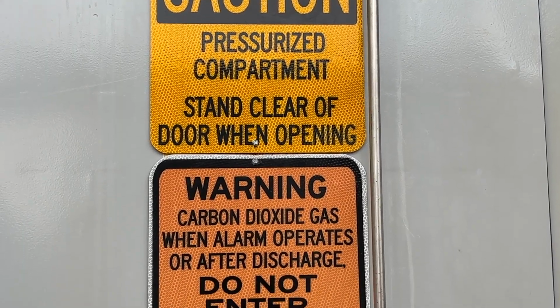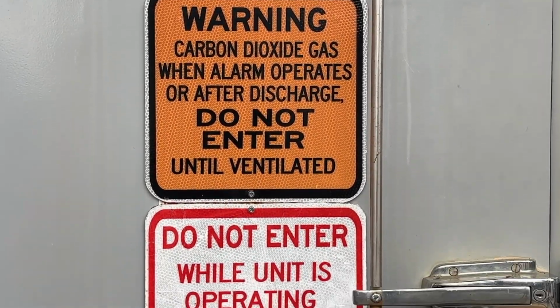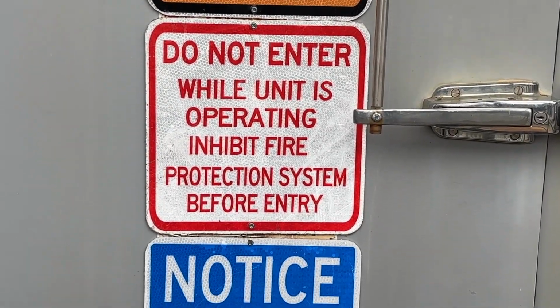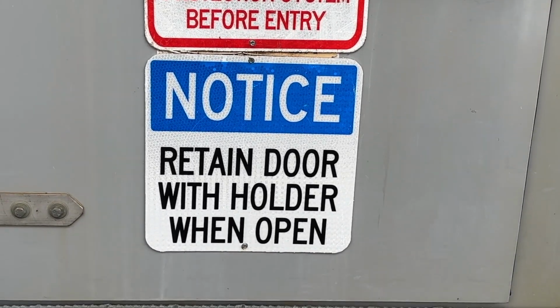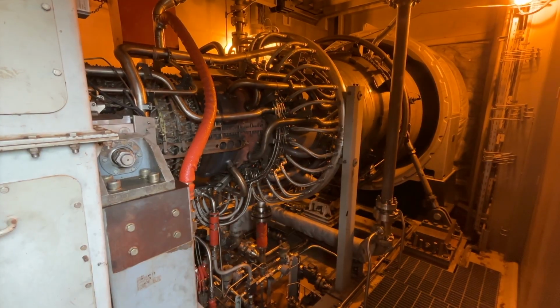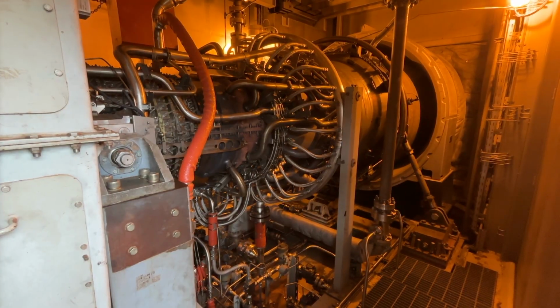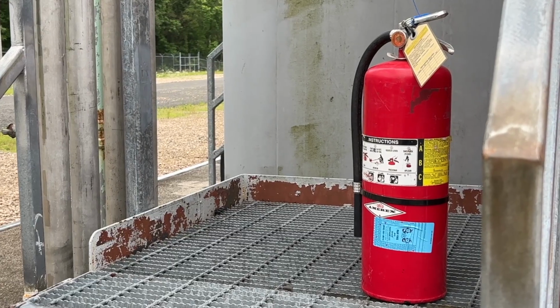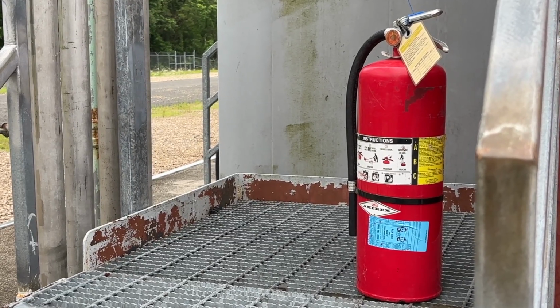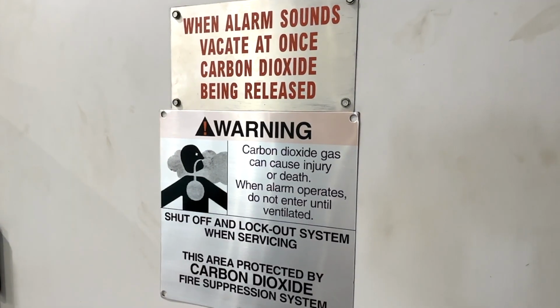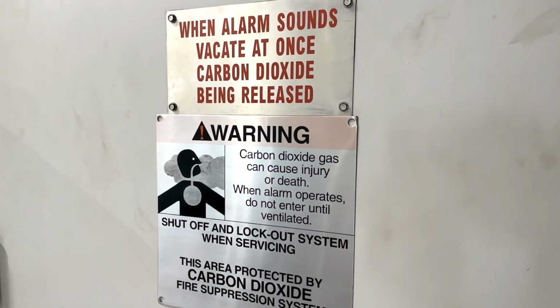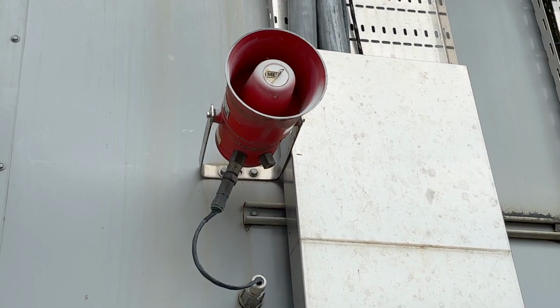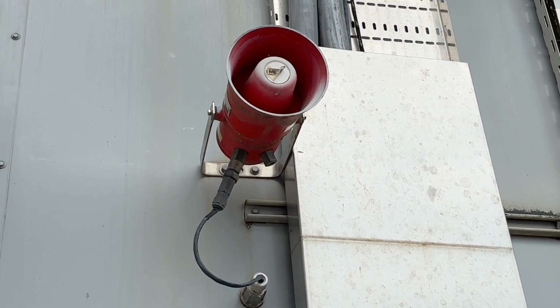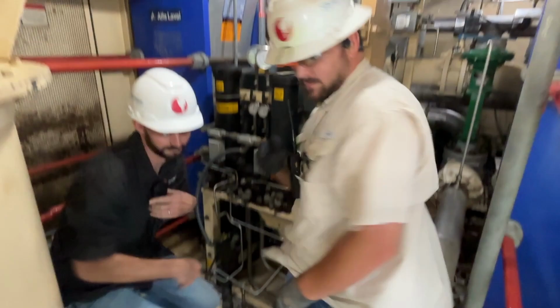In general, if you are working in an area that is protected by an automatically controlled CO2 system, the system will be disabled and valved out of service while you are working, in which case, depending on the nature of your work, you may be required to keep a hand-operated fire extinguisher on hand. In the event of a fire and the automatically operated CO2 system is not taken out of service, an alarm will sound a few seconds before the system discharges. Vacate the area immediately and notify the control room.